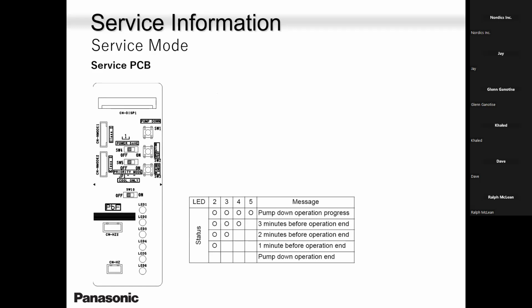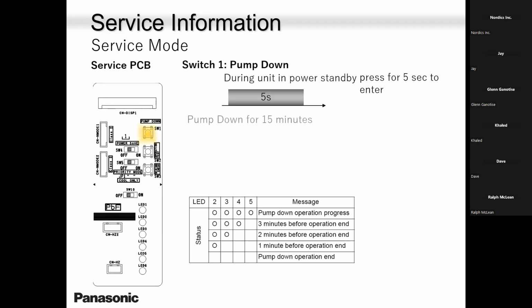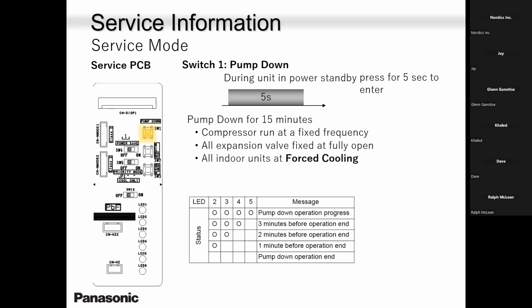All right. So they are the LEDs. They will show you different items based on how the unit is operating. So let's say if we put it into pump down mode, we are running the compressor at fixed frequency. All the EEVs are going to be fully open, and we are going to force the units in cool mode. So you really don't need to be inside the house. As long as the unit has power outside, you don't have to worry about inside.